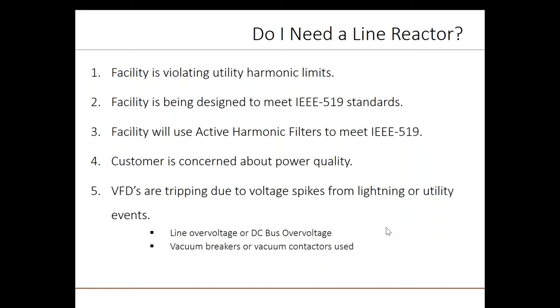Secondly, a facility is being designed to meet IEEE 519 standards. As in the first case, reactors may be the solution or be part of the solution. Third, a facility is being designed for meeting IEEE 519 compliance and active harmonic filters are going to be used. Active harmonic filters, like our HPS TrueWave product, work like noise-canceling headphones. Instead of cancelling audio waves with speakers, an active harmonic filter creates harmonics equal to but opposite those created by the VFDs. Active harmonic filters will benefit from each VFD having a line reactor. If a customer expresses concerns about power quality, their first consideration for minimal costs should be adding line reactors for their VFDs.